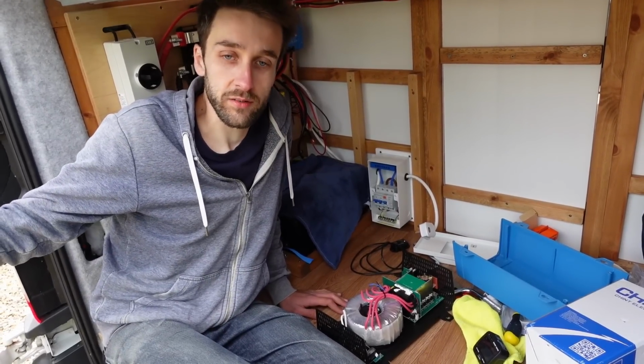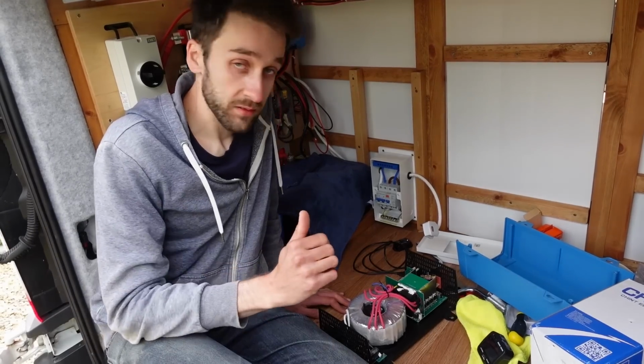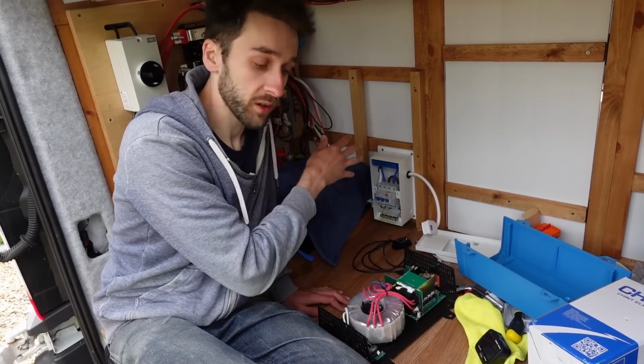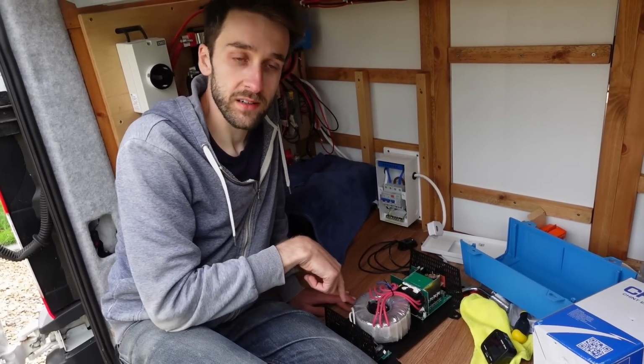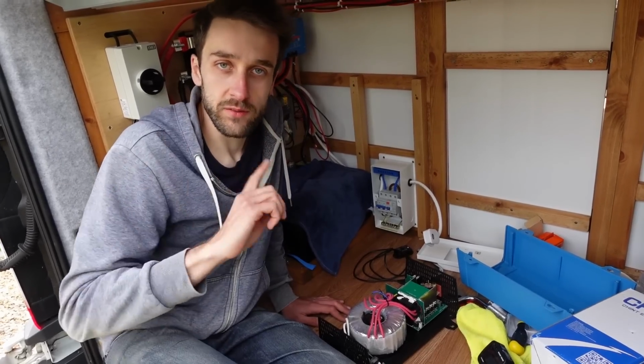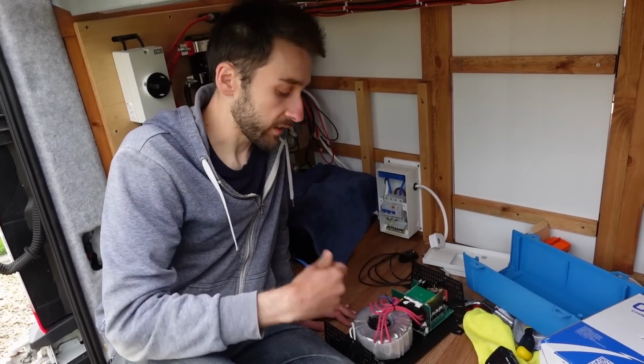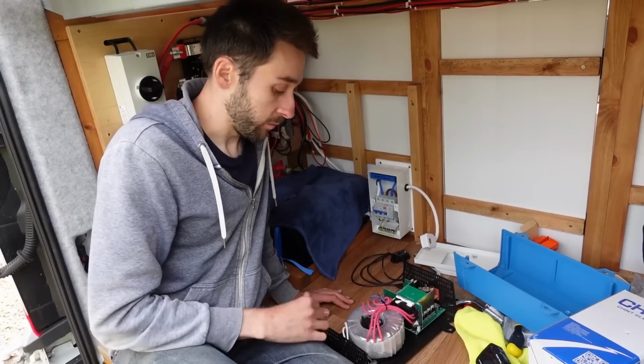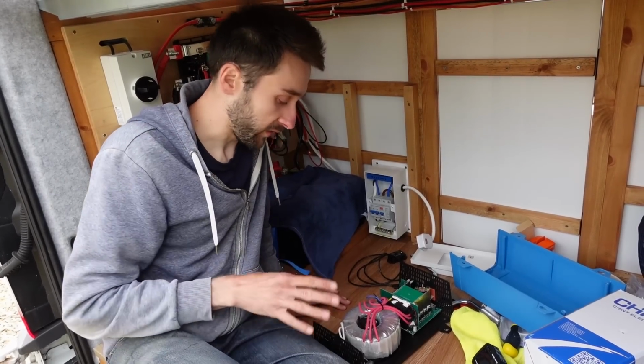So if you've got an inverter charger, when you're plugged into the grid, it uses the neutral earth bond from the electric supply, and as soon as you unplug from shore power and switch to inverting mode, it'll make that connection automatically using a relay. Any time you switch between the two, it just turns on and off that jumper. But for us, with no shore power, we just make that connection once here, and then it should be good to go.